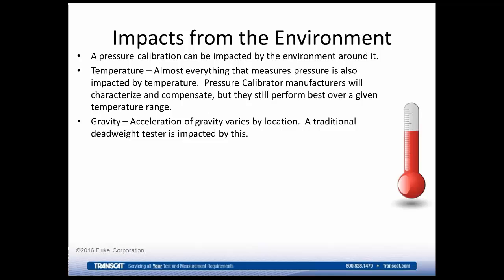Some pressure measurement devices, specifically deadweight testers, are impacted by gravity. The acceleration of gravity will alter the pressure value that the deadweight tester is generating. And that can be by a very large amount without going into too much detail. So one of the ways that the environment impacts our calibration is the local gravity. The acceleration of gravity is different at different locations. And we need to take that into consideration at the location where we're doing the calibration. If our deadweight tester has been built for a specific location for our shop, and we're moving it 100 miles or so down the road, then the local gravity may be different, and we need to take that into account.